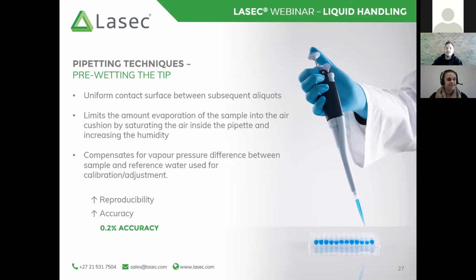Another example of where pre-wetting might be useful is to compensate for vapor pressure differences depending on what samples you are using. Just please do keep in mind that when pipettes are calibrated, we calibrate them to a very specific international standard. The standard will be discussed later in the presentation, but it basically dictates what we need to calibrate with. In this case, we calibrate with distilled or deionized water.